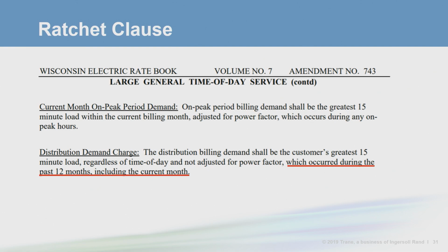Generally speaking, tariffs can be hard to understand, but if you know where to look, they can be helpful. Here we see two definitions for demand charges. The first is for on-peak demand, and the second is for the, quote, distribution demand, which on the bill itself is termed the customer demand. As an aside, it's not uncommon for terminology in the tariff to differ from the names of line items on the bill, like in this case here. These tariffs can be frustrating, but don't just throw your hands up in despair. There's a lot of value if you can figure these terms out.